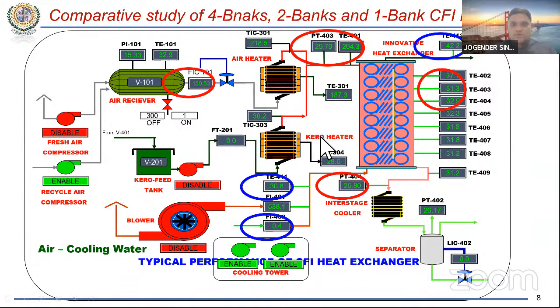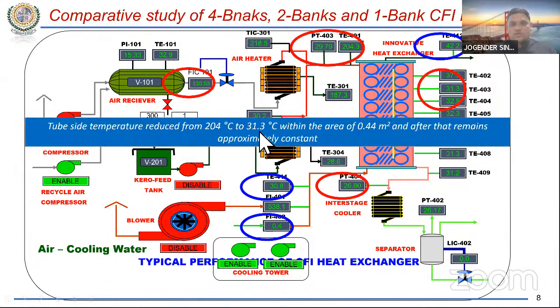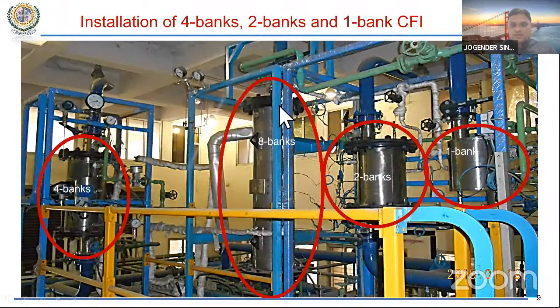So this is what I was talking about. Then 204 to 31 degrees Celsius comes within an area of 0.44 meter square, which is 2 banks. So 31.3, and after that it is pretty much constant. There is no change at all. So we thought, why should we use an 8-bank heat exchanger? We can try with a lower area, with a lower number of banks. So we installed 3 more heat exchangers in our pilot plant: a 4-bank, a 2-bank, and a 1-bank heat exchanger. We repeated all the experiments which we did with the 8-bank heat exchanger, and then we compared the results.